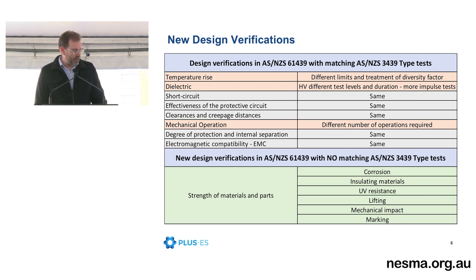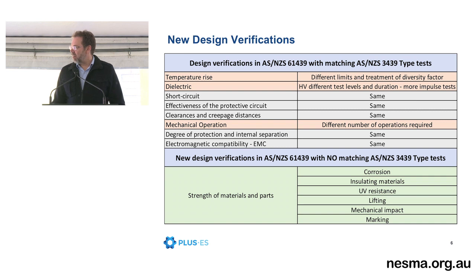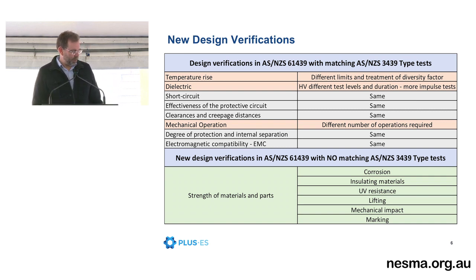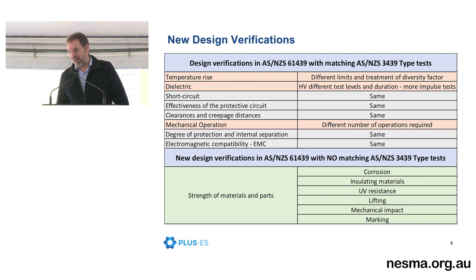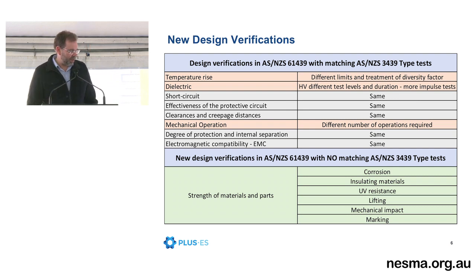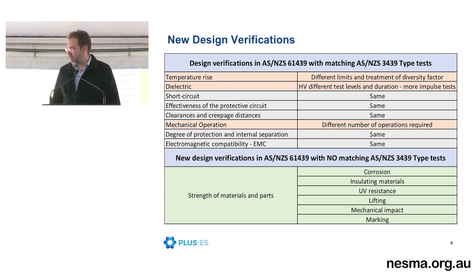So there are some brand new tests that weren't in the old standard. That's the green section at the bottom. They're new design verifications based around the materials. So Max was talking about the glow wire test that affects the insulated supports, and it's in that green section at the bottom. But even though you would see similar tests in the old standard, some of those tests, such as temperature rise and dielectric, are a little bit different. So we can talk about those tests as well.